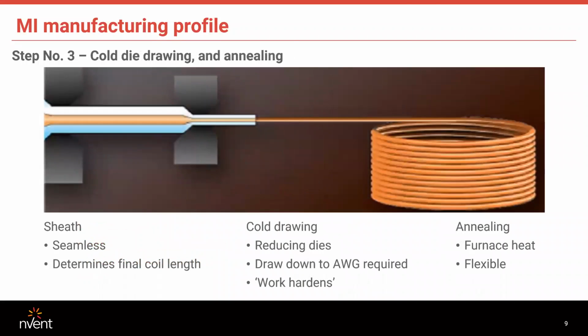And when they're completely full, we take that 30-foot copper tube and pull it through a series of reducing dies. We keep repeating that process until we get to the desired cable size we're looking for. For example, if we're making our 500 kcmil, we'll stretch that 30-foot piece out to 200 feet. If we're making our single conductor number 8, we'll stretch it out to 1,500 feet.